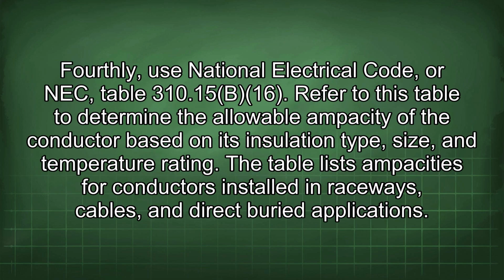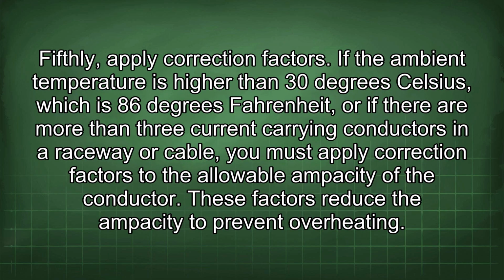Each insulation type has a different temperature rating, which affects its ampacity. Fourthly, use NEC Table 310.15(B)(16). Refer to this table to determine the allowable ampacity of the conductor based on its insulation type, size, and temperature rating. The table lists ampacities for conductors installed in raceways, cables, and direct buried applications. Fifthly, apply correction factors. If the ambient temperature is higher than 30 degrees Celsius, which is 86 degrees Fahrenheit, or if there are more than 3 current-carrying conductors in a raceway or cable, you must apply correction factors to the allowable ampacity of the conductor. These factors reduce the ampacity to prevent overheating.